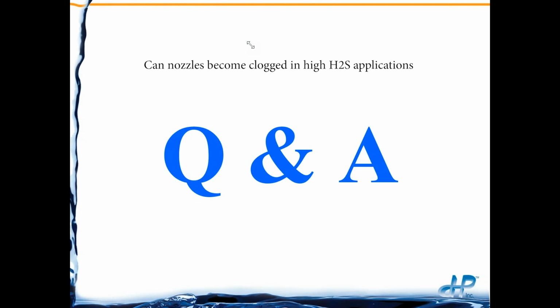Can nozzles become clogged in high H2S applications? Yeah, they can. It also depends on the hydrogen sulfide and some of the other constituents in the water. If the water has other elements in it, we've seen nozzles be plugged before with high hydrogen sulfide that is actually oxidizing even before it gets to the distributor. And also if it has any kind of calcium or scaling process or biological process, that can actually help clean the hydrogen sulfide together.